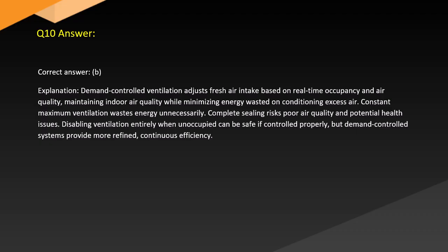Answer. Correct answer, B. Explanation. Demand-controlled ventilation adjusts fresh air intake based on real-time occupancy and air quality, maintaining indoor air quality while minimizing energy wasted on conditioning excess air. Constant maximum ventilation wastes energy unnecessarily. Complete sealing risks poor air quality and potential health issues. Disabling ventilation entirely when unoccupied can be safe if controlled properly. Demand-controlled systems provide more refined, continuous efficiency.